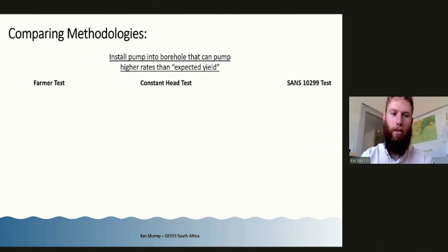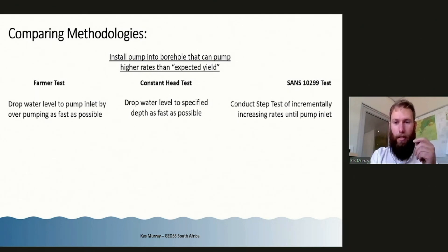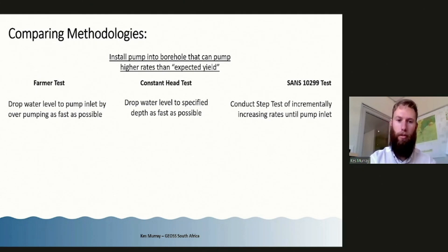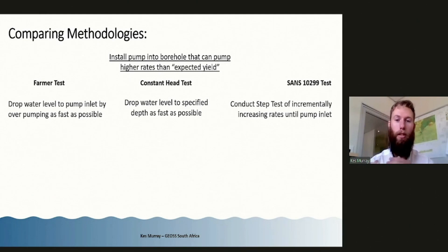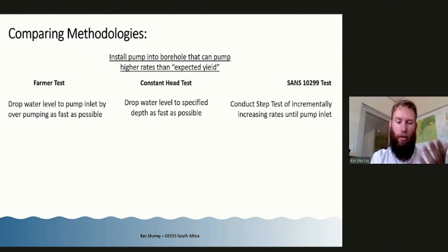Just to quickly go through these methodologies, I have distinguished between a Farmer Test and a constant head test. But in some of my results later on, I'll be amalgamating those and putting them together. Essentially, all testing really should start with putting in a borehole pump that can pump higher than the expected yield. That's sort of where things depart between the two methodologies.